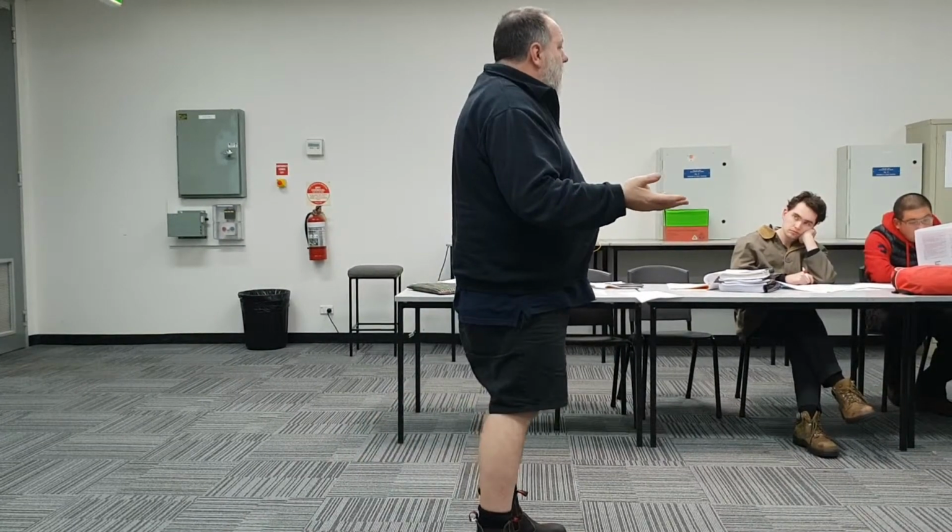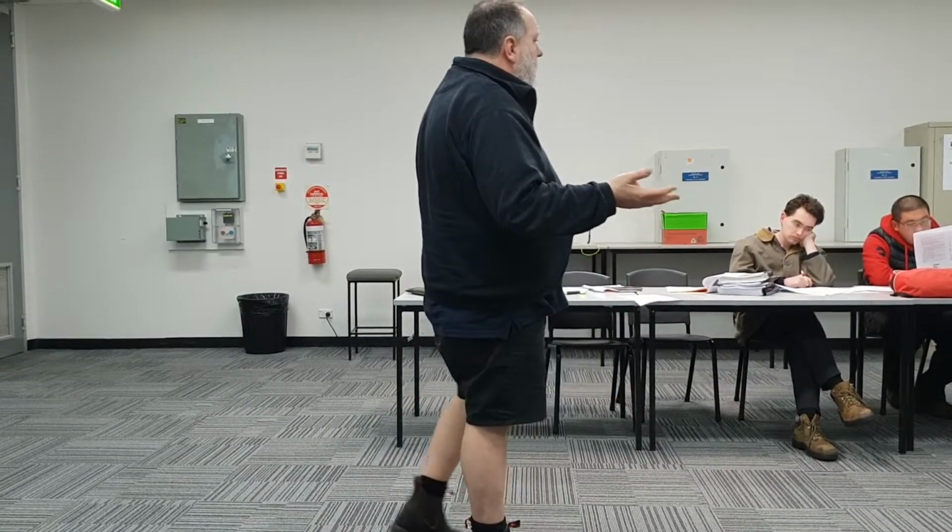That's right. So we're putting in a factor there to allow for mistakes or things turning on. So we've got 0.25 times the number of units. If I've got 6 units, it'll be 0.25 times 6, and then we add the 5 on the end. Does that make sense? So we're working out a value, and then we're adding a bit onto it. Same with the power points.